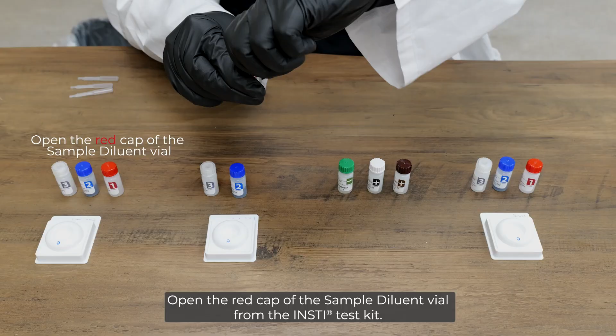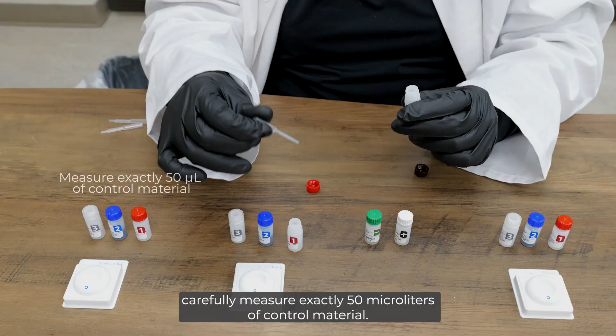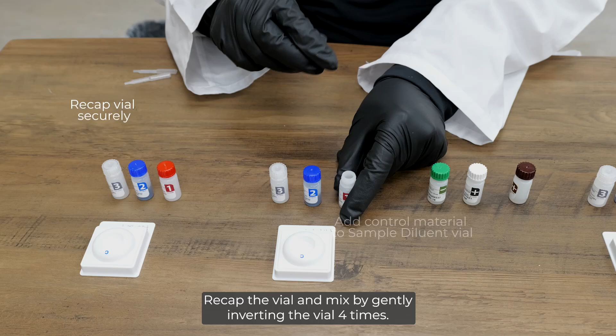Open the red cap of the sample diluent vial from the INSTI test kit. Using a calibrated 50 microliter precision pipette, carefully measure exactly 50 microliters of control material. It is important to ensure that accurate volume is used for reliable results. Transfer the 50 microliters of control material to the sample diluent vial.